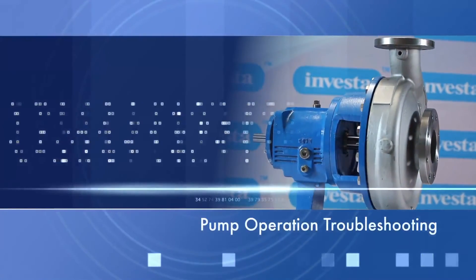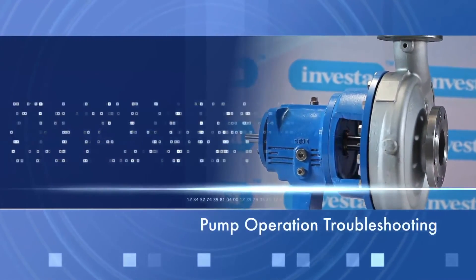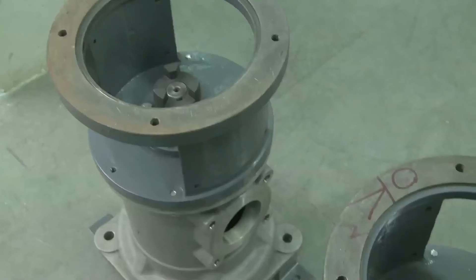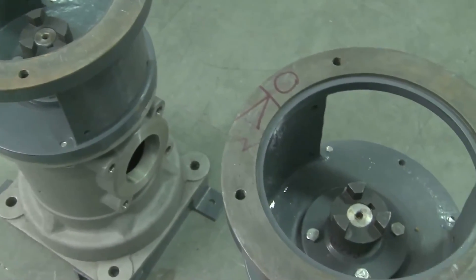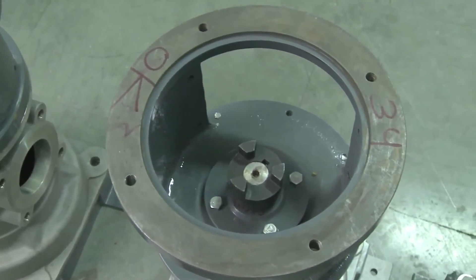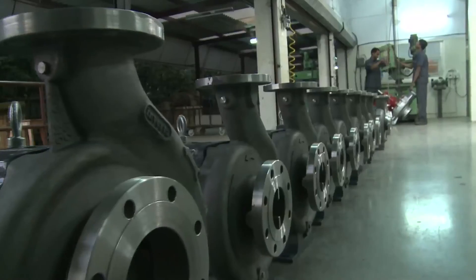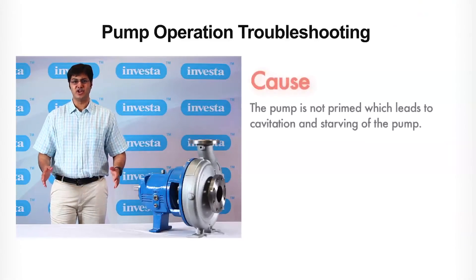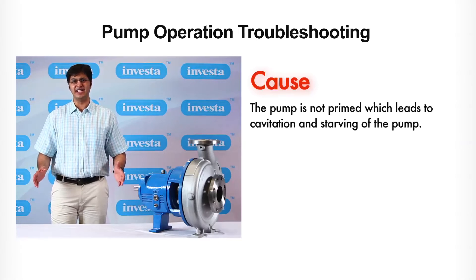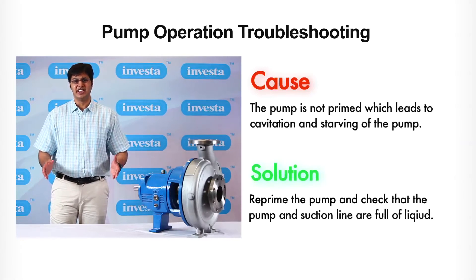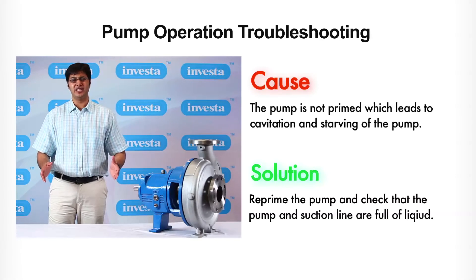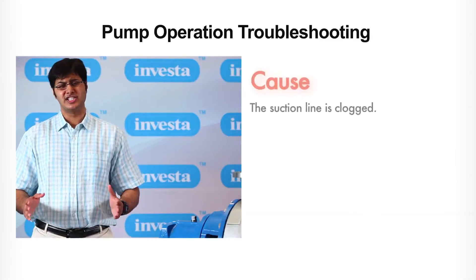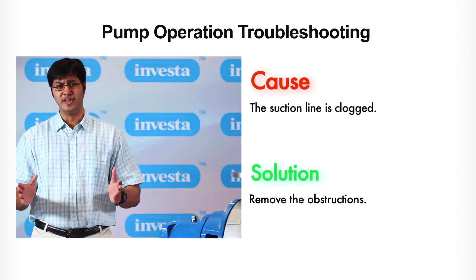Pump operation troubleshooting. Once your pump is installed, assembled and running, you need to be aware of some basic points for troubleshooting in case some common problems occur. We shall look at this in two stages. Number one: the pump is not primed, which leads to cavitation and starving of the pump — re-prime the pump and make sure that the pump and suction line are full of liquid. Number two: the suction line is clogged — remove the obstructions.